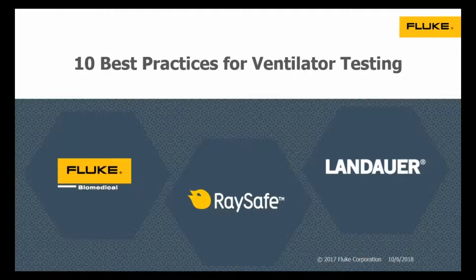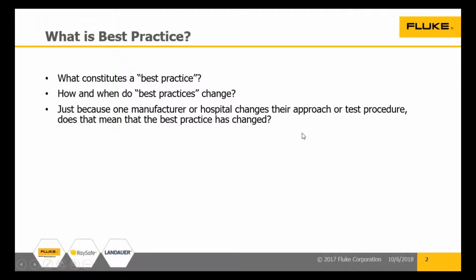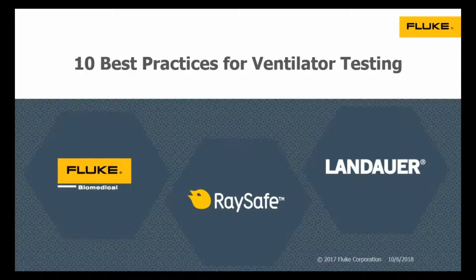How many of you test aspirators? Okay. How many of you test endoscopic insufflators? Okay. How many of you test flow meters that plug into the head wall or the ceiling? All right, how many of you test the argon gas output of an electrosurgery unit? All right, so you are testing medical devices that exert gas pressure and produce gas flow. You deserve to have a test instrument that will let you do all of that. Okay, good. Yep. Thank you.